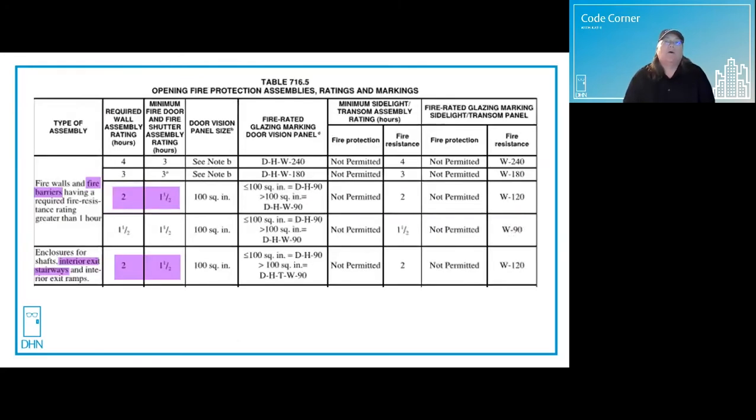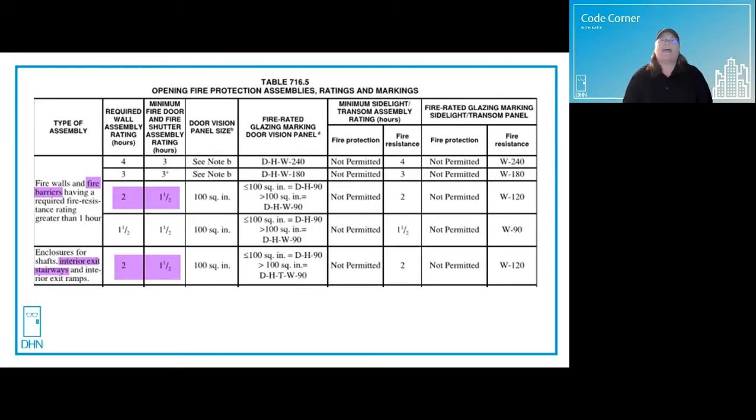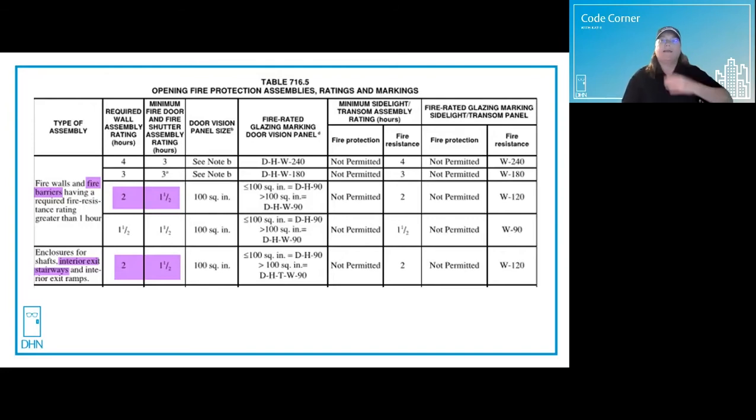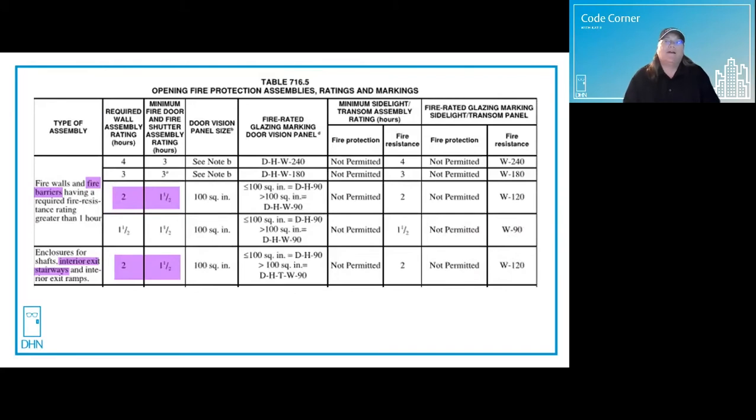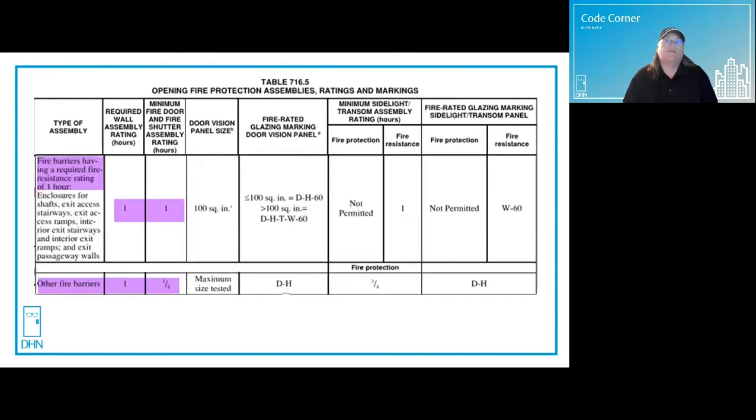For the most part, fire barriers will either be rated for one or two hours. Fire barriers protecting enclosed exit stairs and horizontal exits will be one hour rated when connecting a building three stories or less, and two hour rated when connecting a building four stories and higher. Fire door assemblies will be classified as B-labeled, either 90 minute for two hour walls or 60 minute for one hour walls.